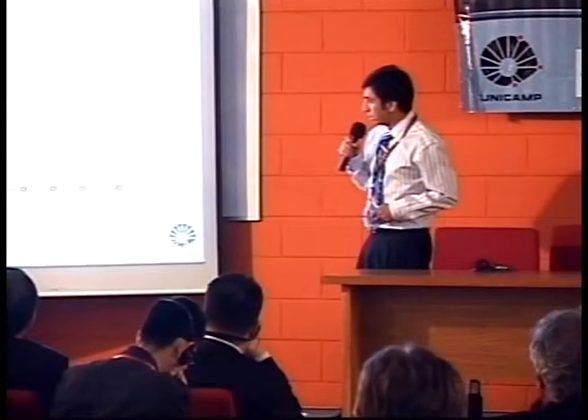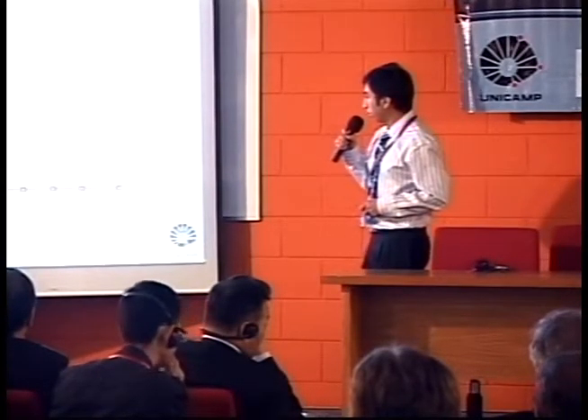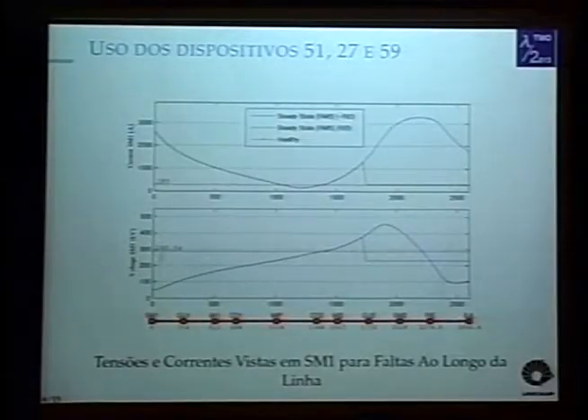we also analyzed the voltages and currents seen in Serra da Mesa 1 for faults throughout the line. Here we have the voltage seen in Serra da Mesa 1 without the reduced insulation distance, and in green you have the voltage using the reduced insulation distance. And in pink we have the voltage in stationary states without fault. In the beginning of the line we have the expected behavior. We have a fault and the voltage goes down a lot. And as the fault becomes more distant from the sending station, voltage increases. This is what would be expected.